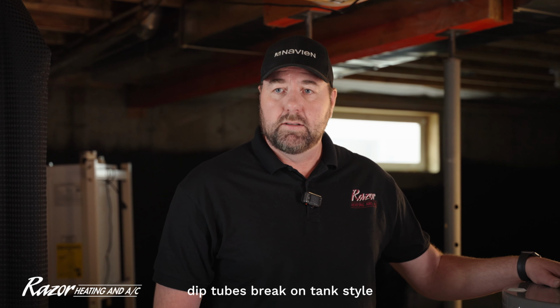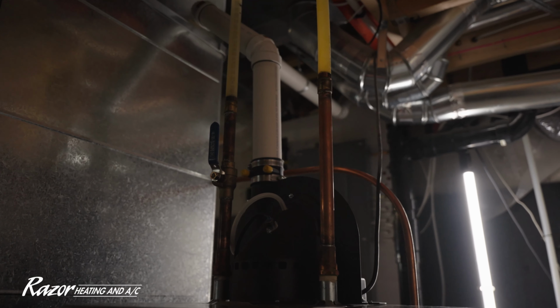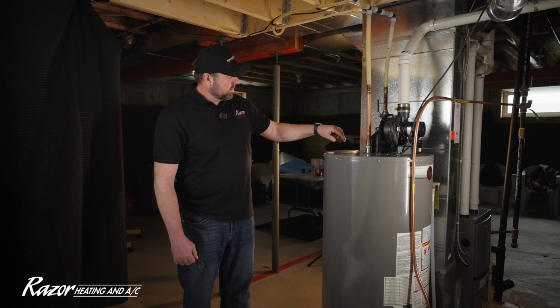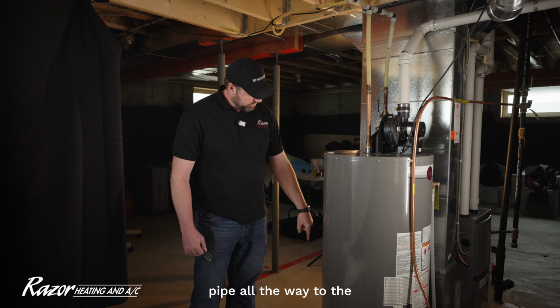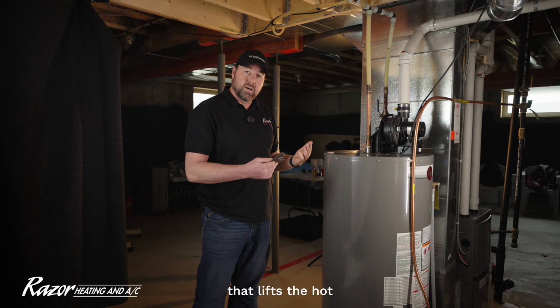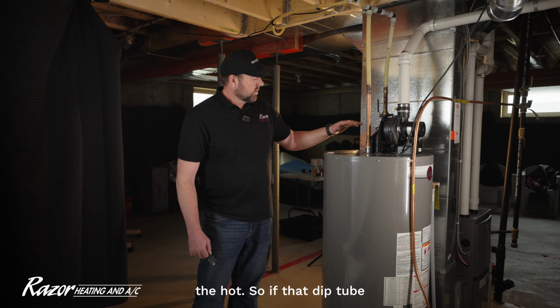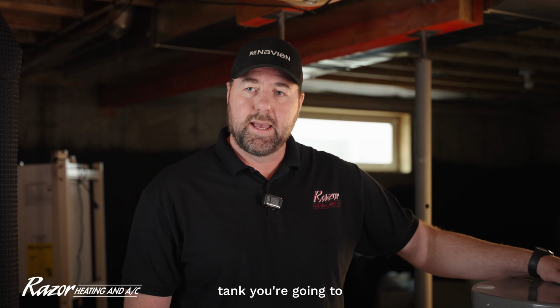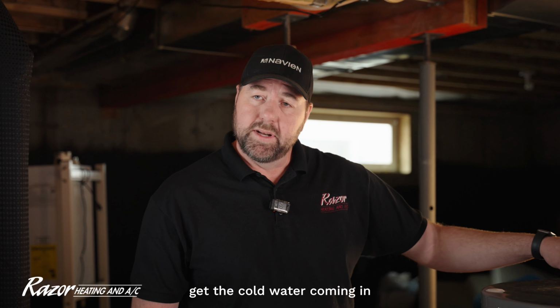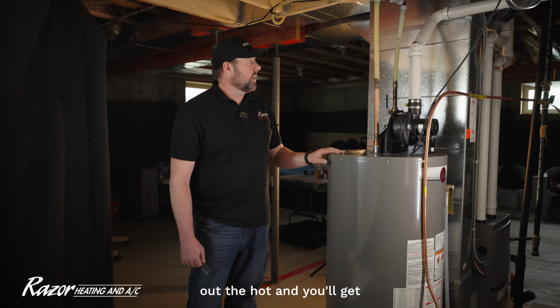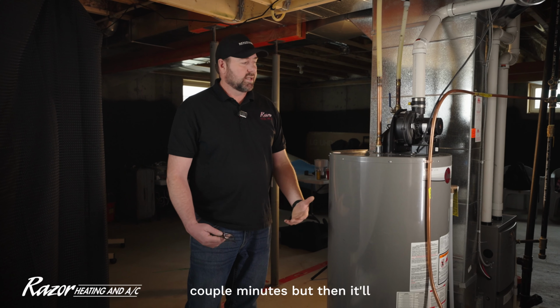We see dip tubes break on tank style water heaters periodically. Basically, the cold water comes in on the cold, goes through a pipe all the way to the bottom of the tank, and then that lifts the hot water out of the tank through the hot. So if that dip tube breaks off in the tank, you're going to get the cold water coming in and then immediately comes out the hot, and you'll get hot water for a couple minutes, but then it'll go cold.